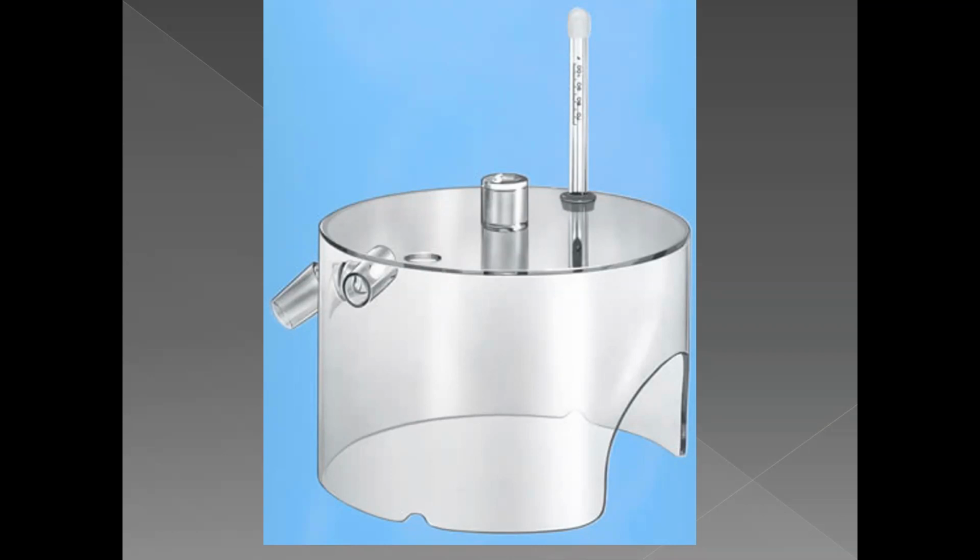Why does increasing flow make a difference? Want to flush out the... Very good, yes. So room air is coming into the hood and you need more flow. So that's why fixing that problem would require increasing the amount of flow going into the hood.